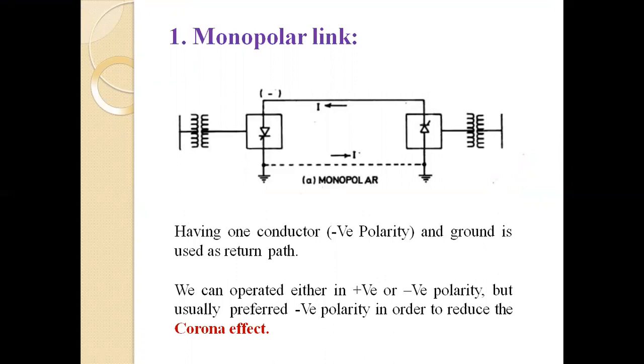First, in the monopolar link, the circuit shows the monopolar link. It is the source. Here is the converter, which converts the AC into the DC. A single line is connected, and again the converter is at the receiving end, which converts DC into the AC. So in the monopolar link, there is one conductor of negative polarity and the ground is used as a return path. We can operate with either positive or negative polarity, but we usually prefer negative polarity in order to reduce the corona effect. For reducing the corona effect, we take the negative polarity, and positive as a ground.